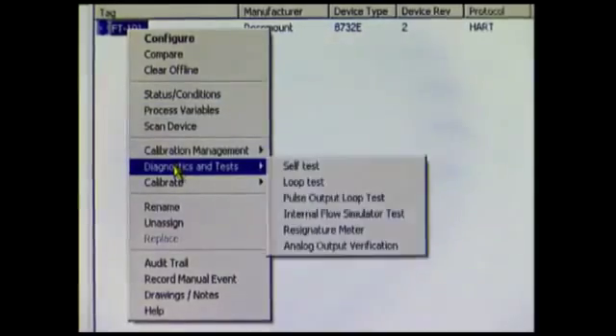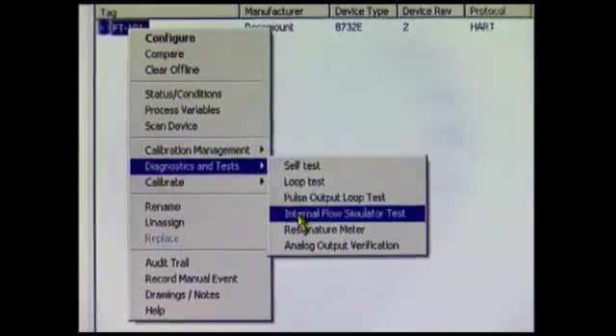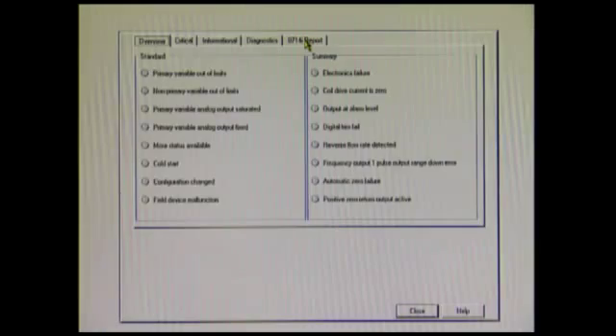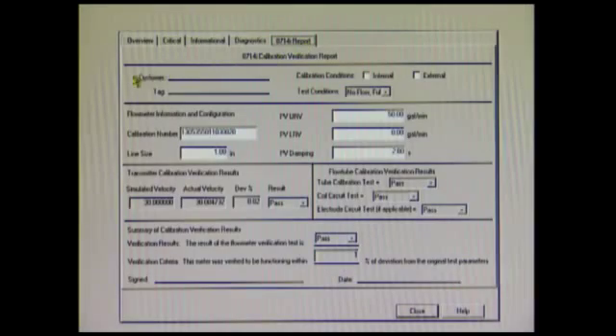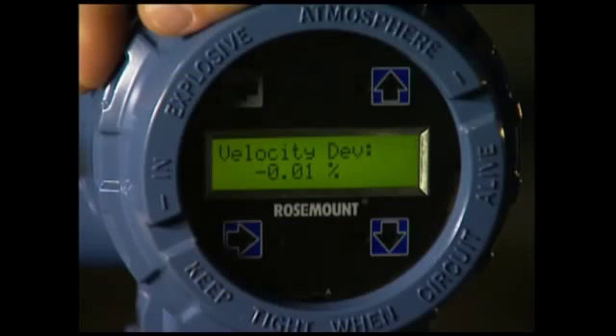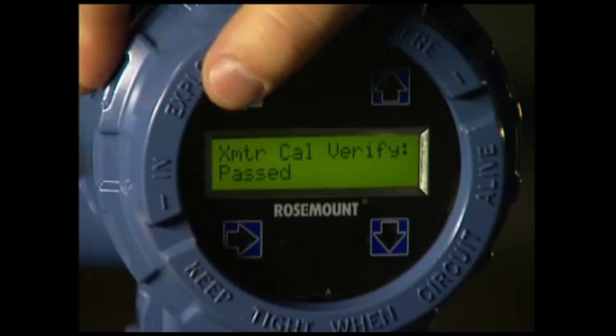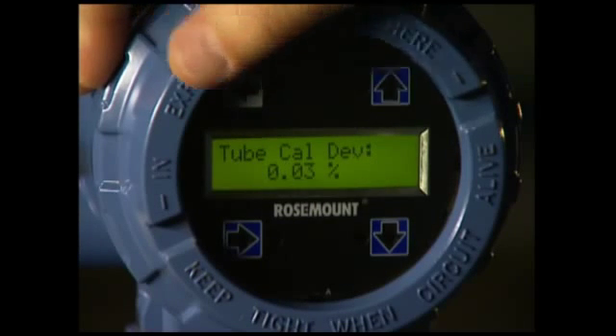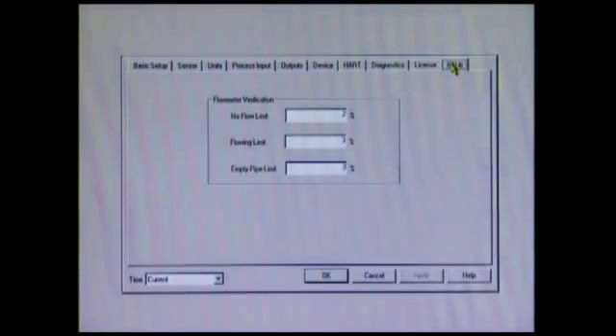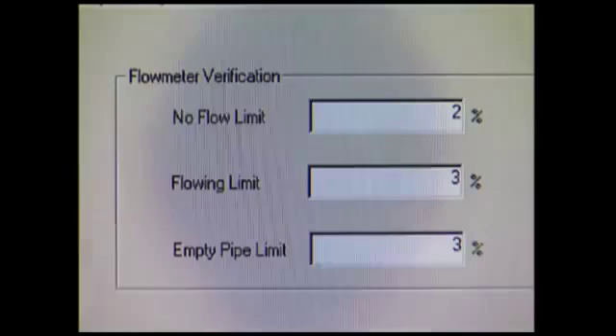With the 8714i diagnostic, you get a simple and straightforward method for running the verification that provides documented pass-fail results from the test, including quantified calibration deviation values for both the transmitter and the flow tube sensor. It's all tested to the pass-fail criteria you set for the application and conditions.